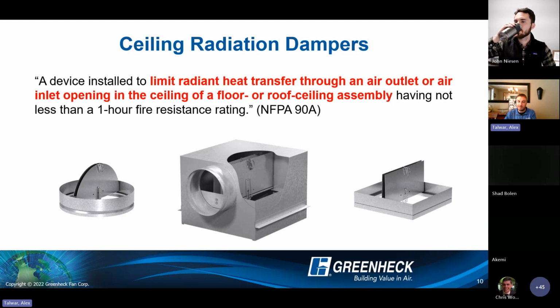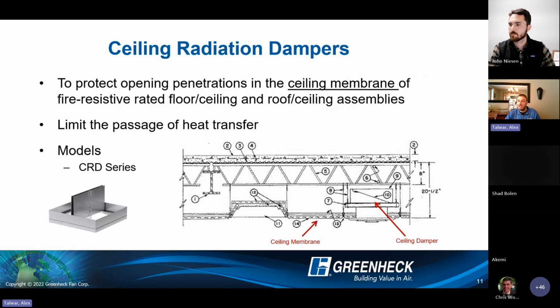So a little bit different purpose, similar sort of construction, but due to the nature of the test, you can end up making them out of a lot lighter gauge material, and being that you're only limiting heat transfer and not necessarily trying to restrict flame, although that would certainly make it difficult to pass a test as well, of course. But yeah, different purpose, different product. They are protecting the ceiling membrane of a floor ceiling or roof ceiling assembly.